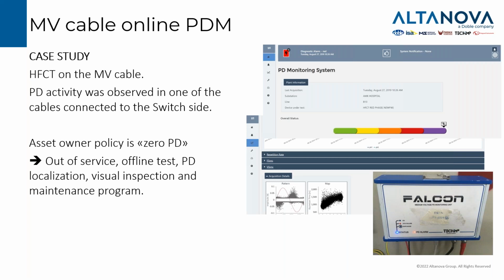composed of several steps. First, there is a confirmation of the PD from the customer expert. Then there is an out of service offline PD test for localization. Once the defect is localized, there is visual inspection and maintenance. So you can see how the structure of the maintenance has its own advantages, and it was a very efficient way to manage the information received and to plan proper activities.